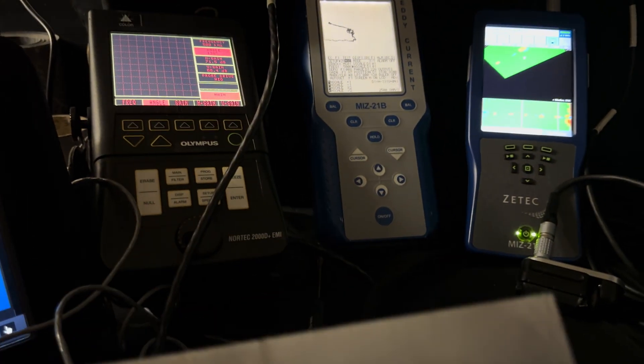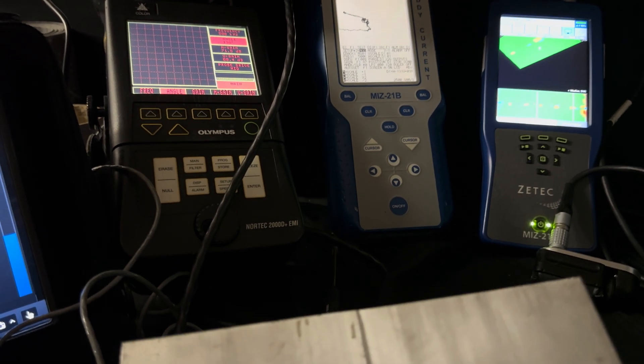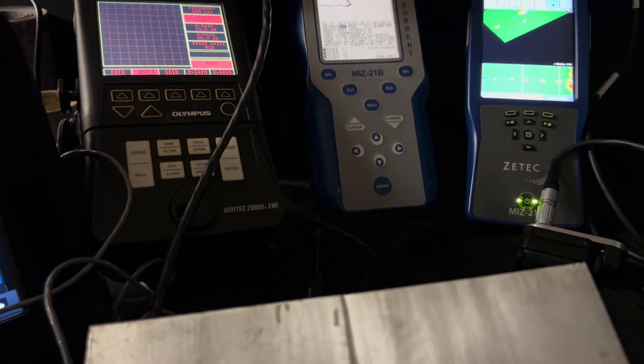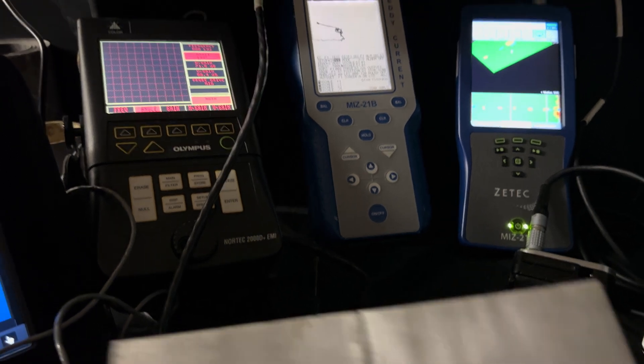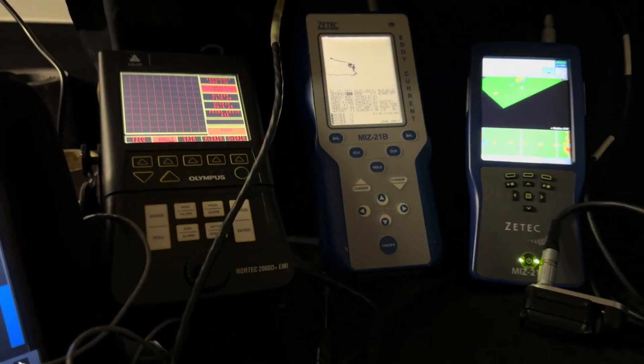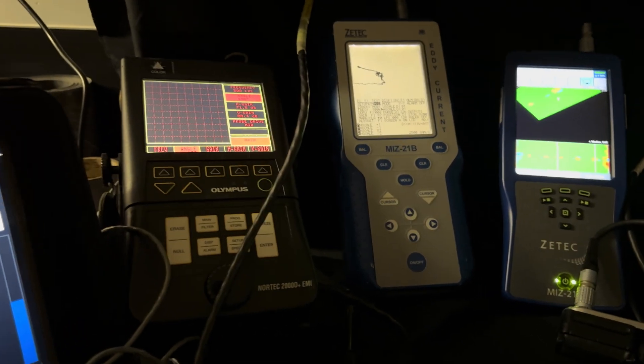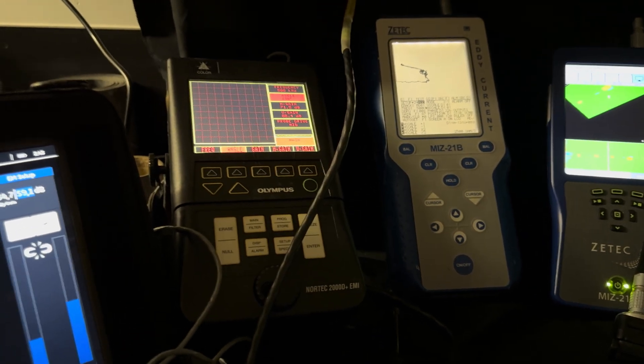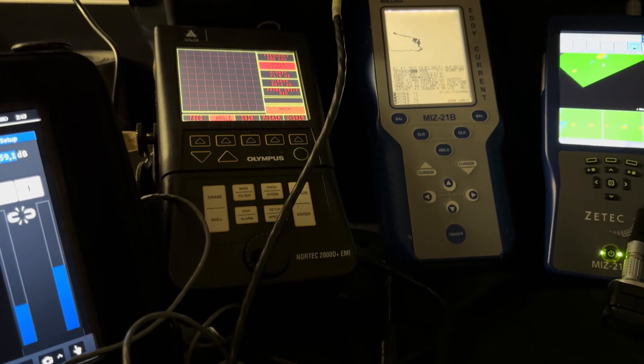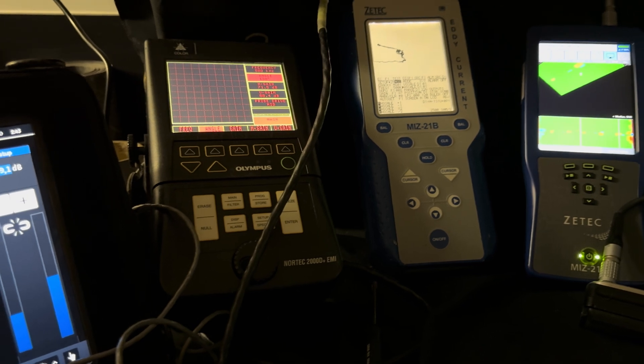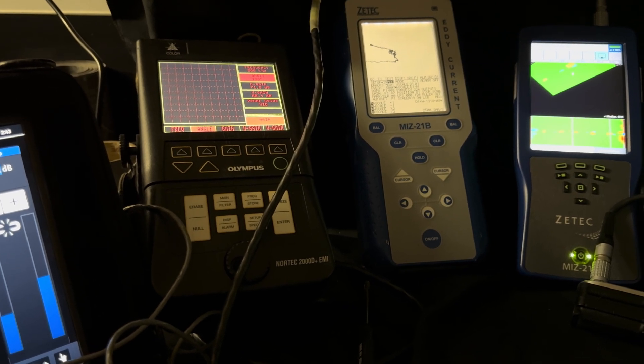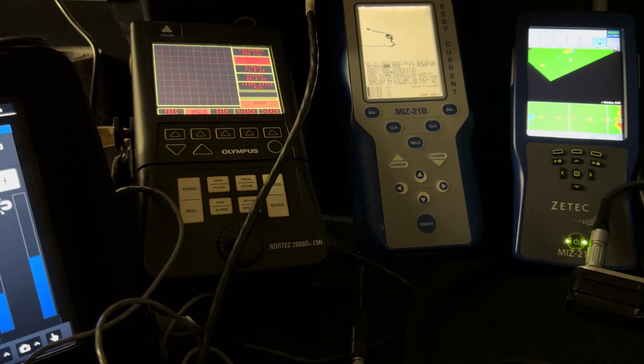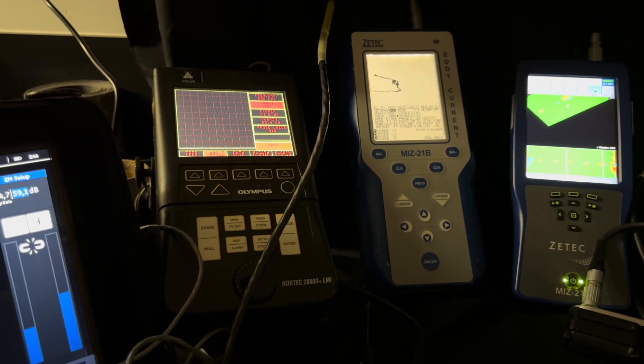Now I want to start off by saying calculations for test frequency, or if you're using a slide rule, are not always gonna be the same. It's gonna vary not only by test instrument, cables might have something to do with it, of course the material and the thickness has a lot to do with it, which coil size has a lot to do with it, conductivity, the material permeability.